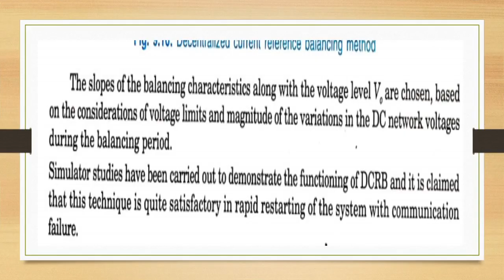In this method, each converter is provided with 2 automatic current regulators and 1 voltage regulator. The rectifier and inverter control characteristics are shown in the figure. During the normal mode of operation, the rectifier station with the lowest voltage reference or the inverter station with the highest voltage reference acts as the voltage setting terminal.